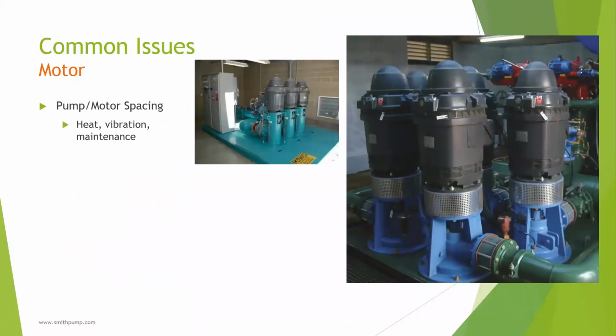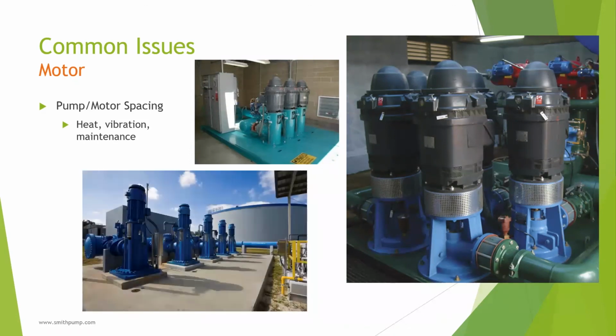So let's talk about equipment spacing. This can easily be overlooked when trying to squeeze all the equipment into the smallest building possible. The above pictures are good examples of future headaches waiting to happen. Problems related to heat, vibration, and maintenance can occur. Here's an example with better spacing layout for heat, vibration, and maintenance. So motors blow air to cool down, but tightly packed motors will draw in hot exhaust from their neighbor. Excessive heat buildup will lead to shorter motor life. Pumps can shake the ground if the structure mass is not adequate for the application, or one bad pump could transmit vibration to nearby operating units if spaced close enough. Finally, the not so obvious issue is future maintenance. And I wouldn't want to be the maintenance guy for the 5 units packed this tight.